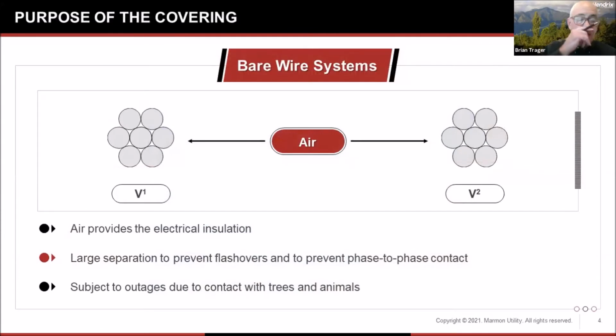Talk about the theory. I just have 3 slides. Basically, when we're using bare conductor, we're using air in between those phase conductors for the insulation. Air is a halfway decent insulator, but we need a whole bunch of it. So we need to keep a pretty large separation between those phase conductors. But even though we do have a good amount of insulation between those bare wires, we're still subject to outages due to contact with trees, animals, etc., or phase conductor to phase conductor contact.